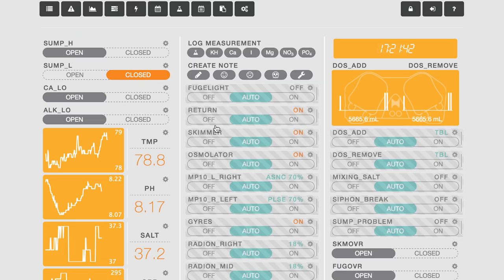Before showing the safety checks in action, I want to walk through some of the code you should have if you're running a system like mine. First, this is my high sump optical sensor and my low sump optical sensor. By Apex default, if sensors are wet they're closed; if they're dry they're open. This shows the high level sensor is open — dry — and the low level sensor is wet.